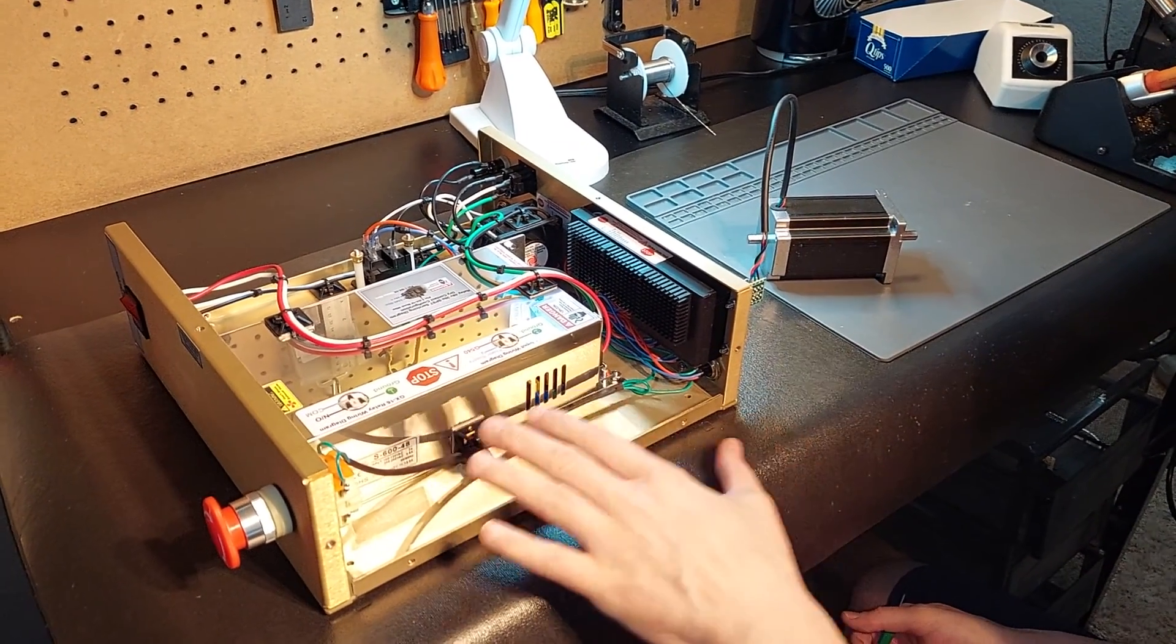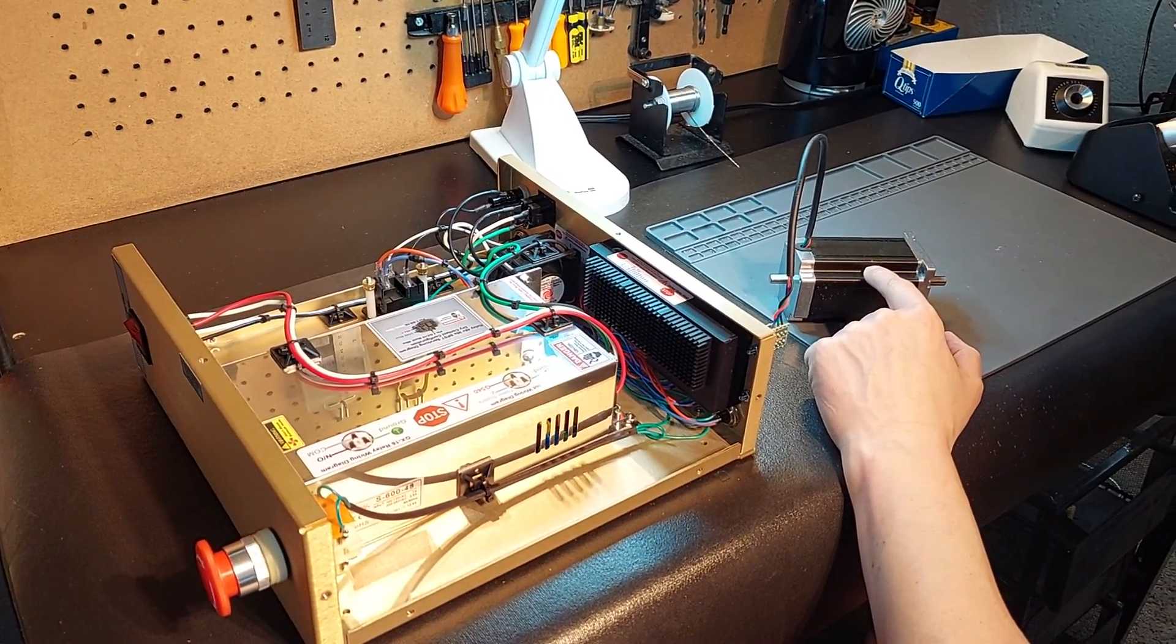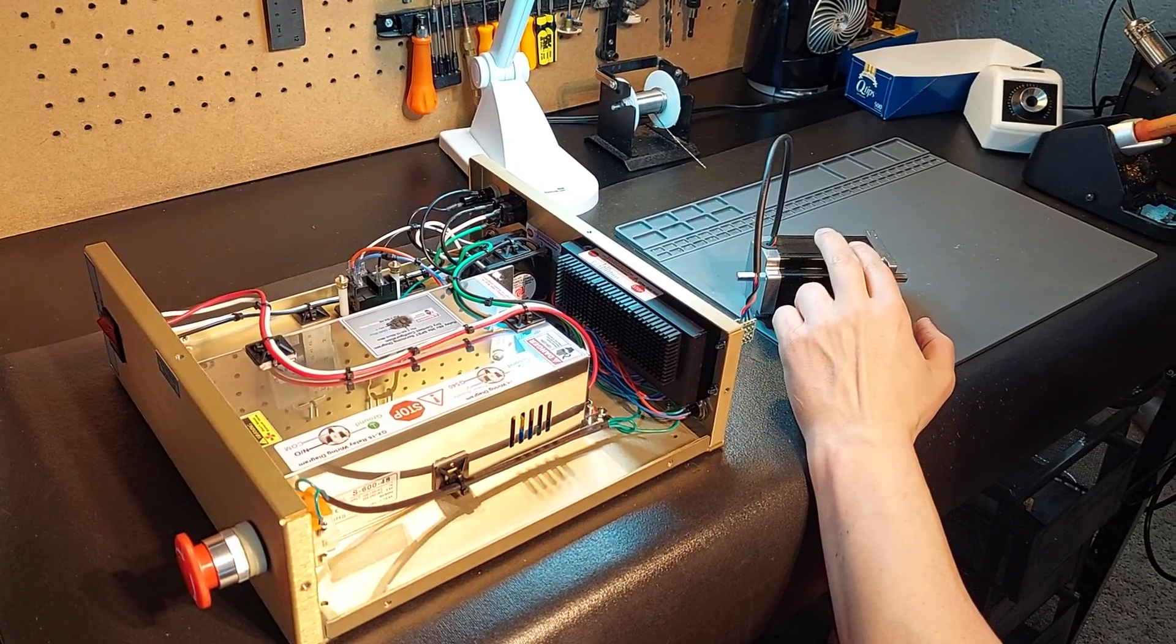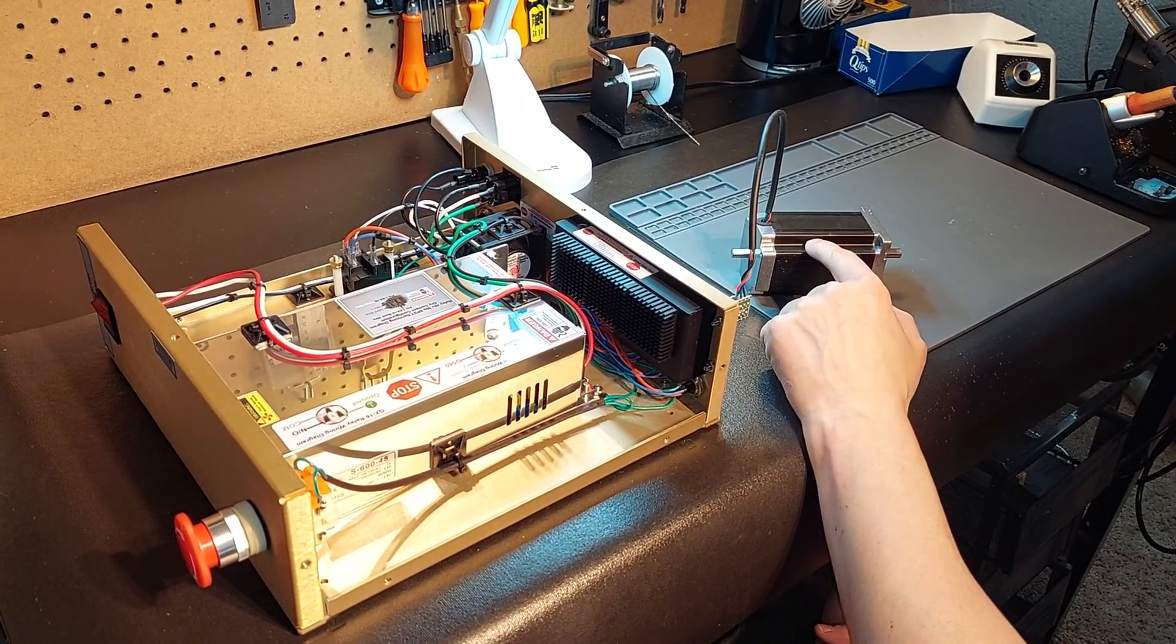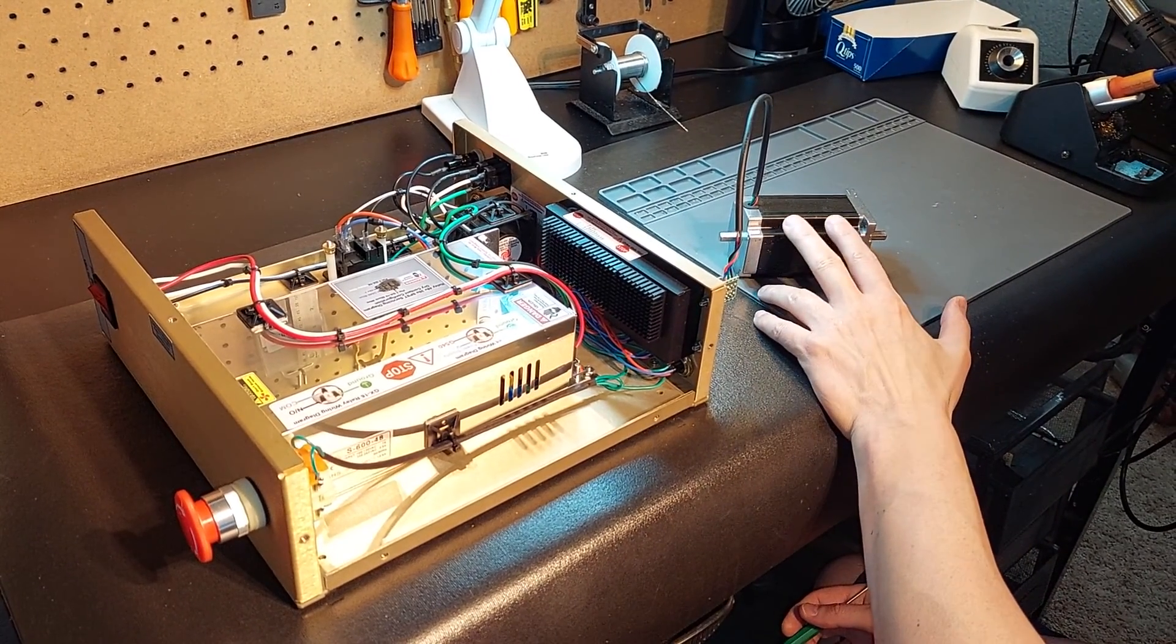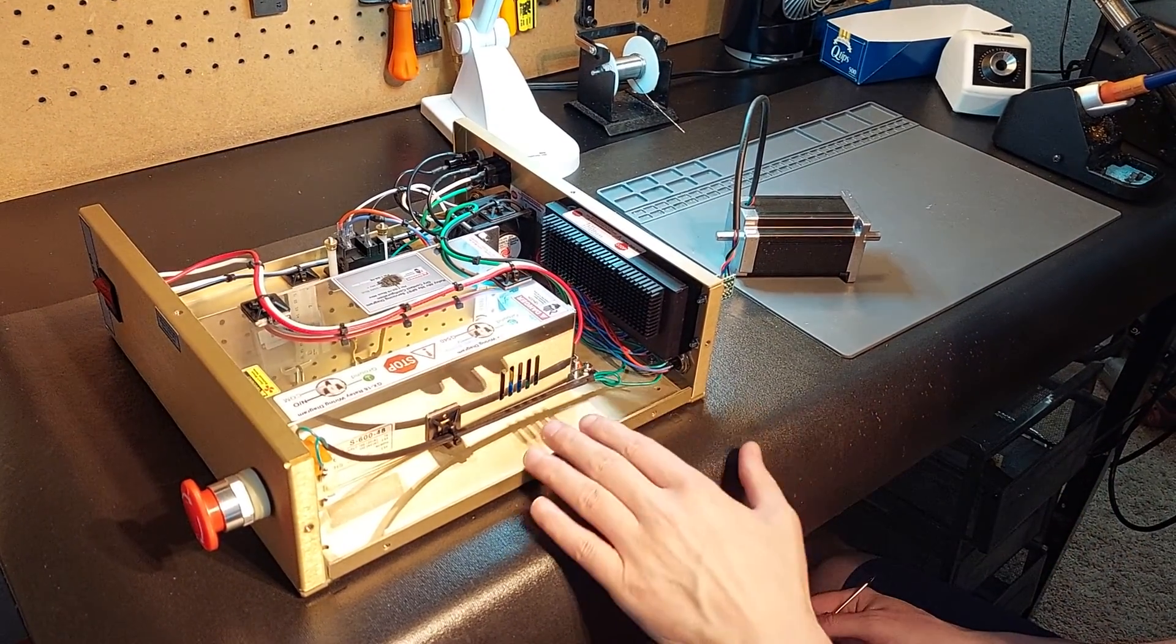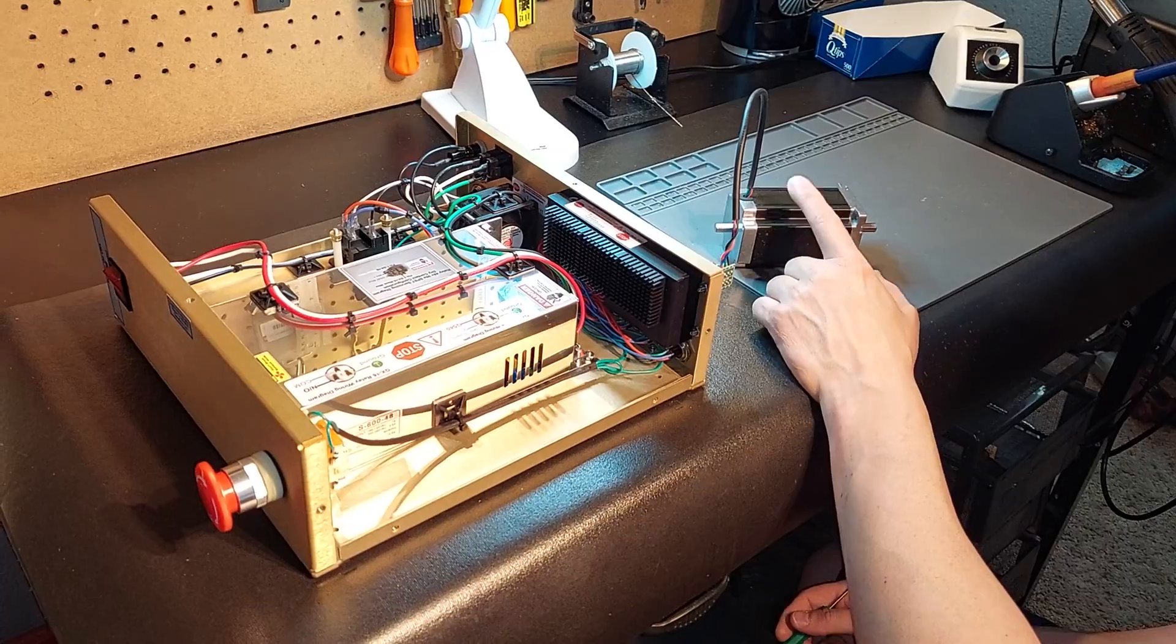So if we run 48 volts, which is what we've got in this system right here, this 600 ounce motor is going to get very hot because we're using overdrive ratio. For those of you not familiar with overdrive ratio, it's where you're actually overpowering a stepper motor from its rated voltage amplified by up to 25 times the voltage that it's rated to. And the reason we say up to 25 times is because if you go higher than that, you risk potentially damaging the motor because of excess heat. The byproduct of voltage is heat. You'll get more speed, but then you have to dissipate more heat.